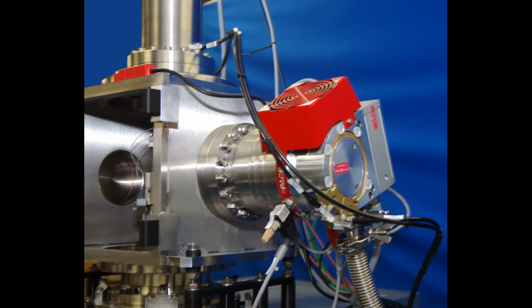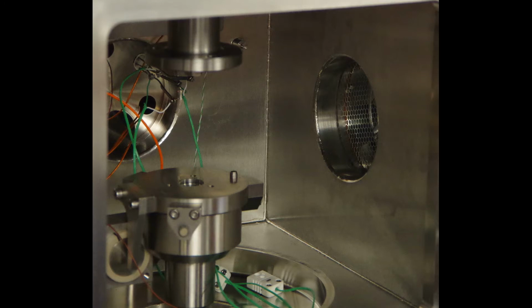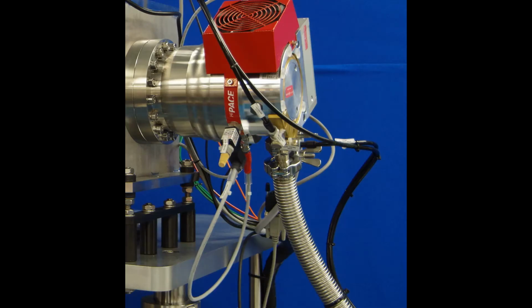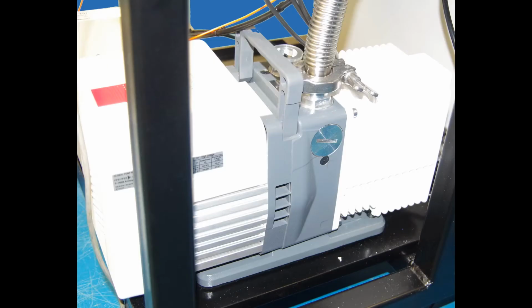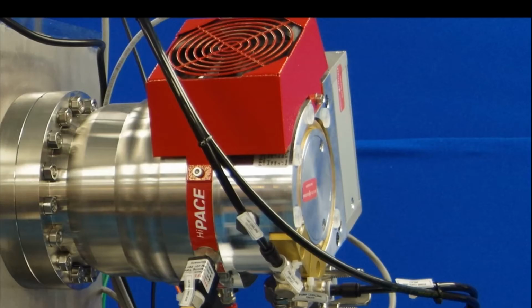A turbomolecular pump with a cooling fan is fitted on the right hand side of the chamber. The pump has ports for water cooling connected to the manifold on the back of the machine. Inside the chamber there is a mesh to protect the pump from ingestion of debris. The pump is connected by a stainless steel hose to a roughing pump. The vacuum system is controlled by a unit mounted on the back of the pump, which is controlled by the PC.